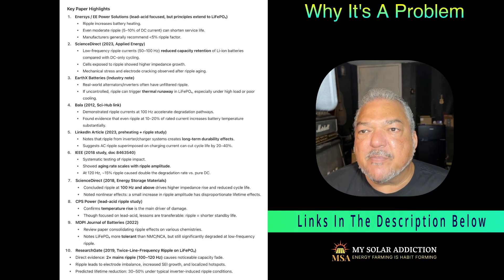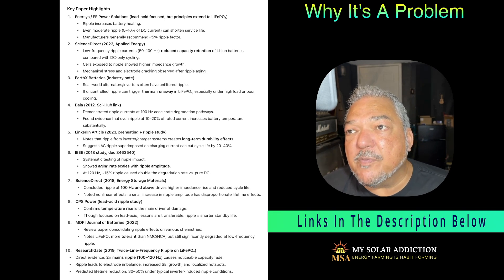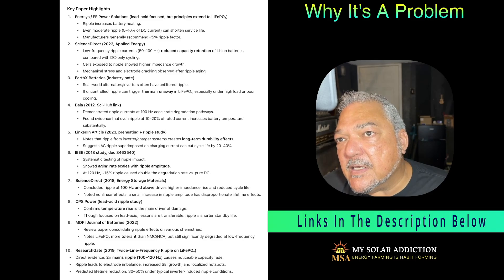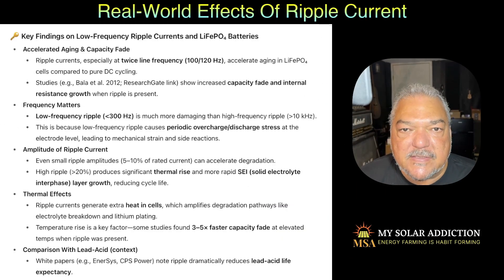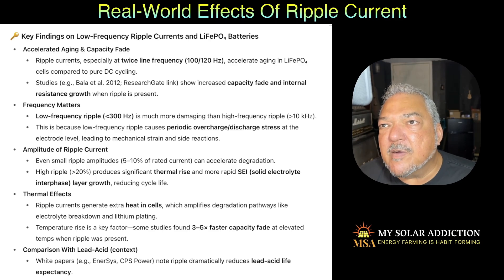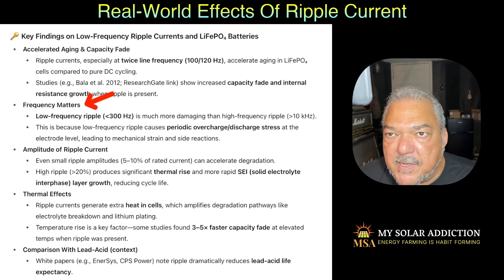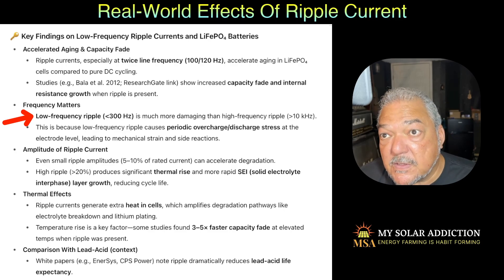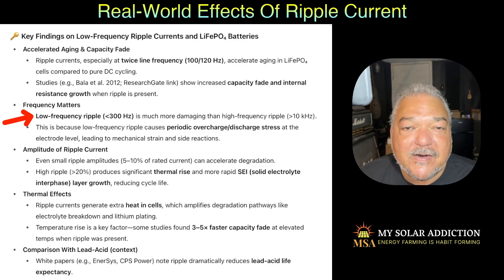Here is a list of 10 of the top articles I found on ripple current — some about lithium-ion, some about lead acid, and a lot about LiFePO4, which was my main concern with my current inverters. From the key findings on low-frequency current ripples caused by inverters: you get accelerated aging and capacity fade. The 100 to 120 hertz range seems to be one of the hotspots. Frequency matters — lower frequency ripple is worse. Below 300 hertz is a bad frequency for ripple; above 10 kilohertz it's not anything to worry about. Low-frequency ripple causes periodic overcharge/discharge stress at the electrode level, leading to mechanical strain and side reactions.